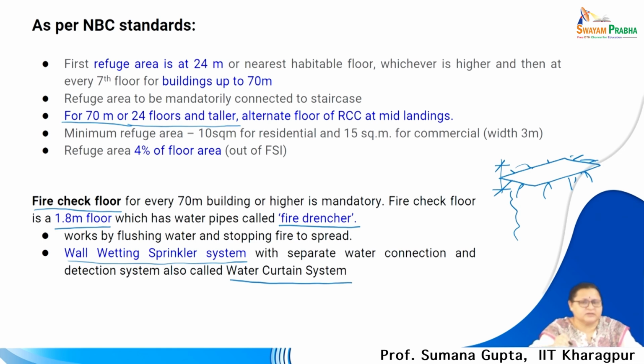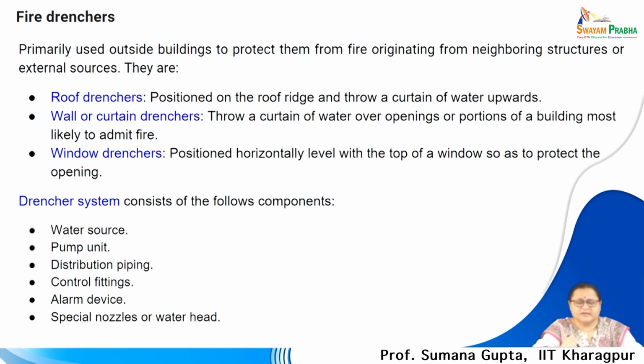We had discussed it in sprinkler systems, I think in module 4. So, these fire drenchers can be from the roof. If it is 70 meters, it may be at intermediate levels, because tall buildings can go as high as 828 meters, which is Burj Khalifa. So, it will have so many 70 meter breaks. Such systems at 70 meters or lesser are to be inbuilt within the building system to wet the facade, so that the fire cannot move further up.